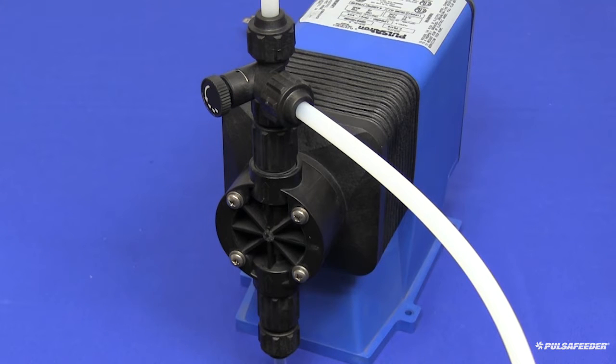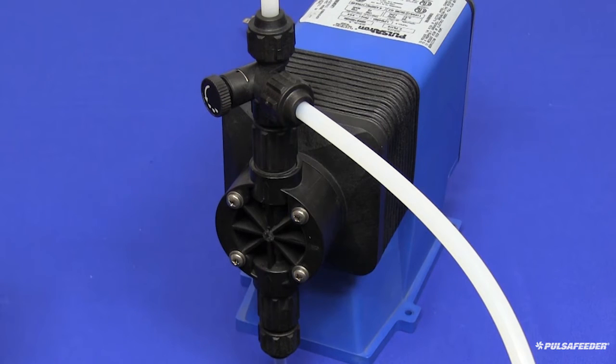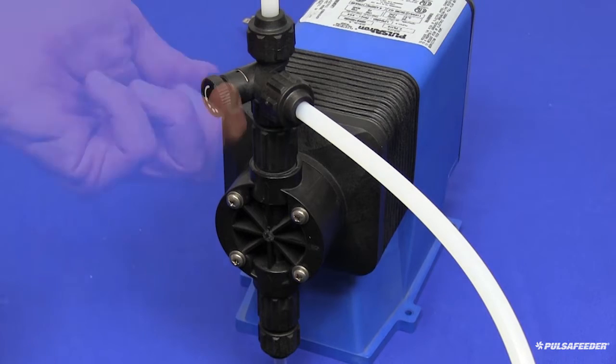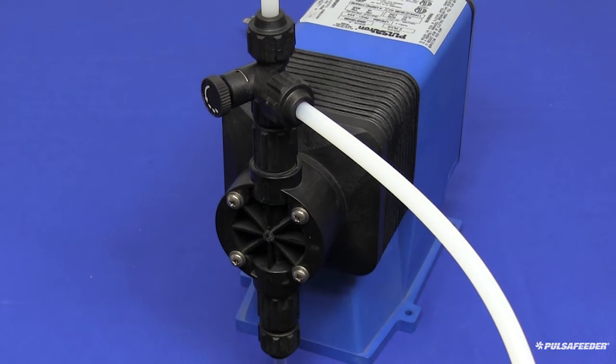You will need to have your pump depressurized. Make sure relief tubing is connected to your bleed valve or 4-function valve if your pump is equipped with one, and tubing is inside your solution tank. Turn the bleed valve counterclockwise until the pressure and liquid has drained back into your tank.